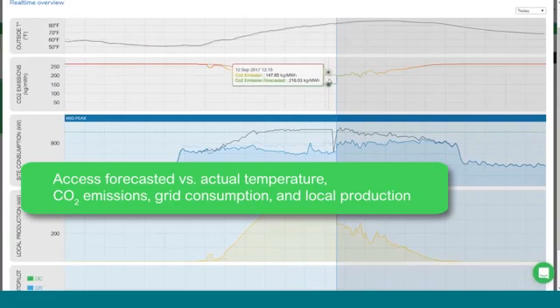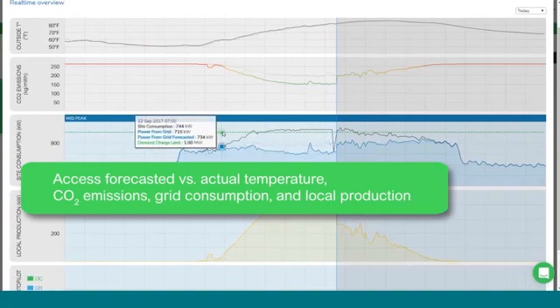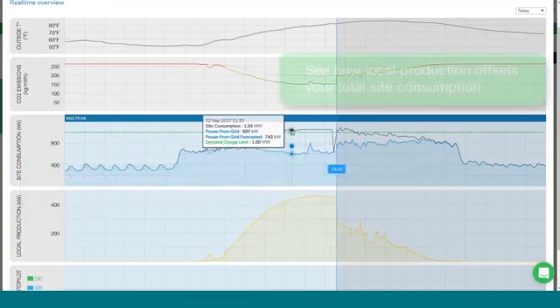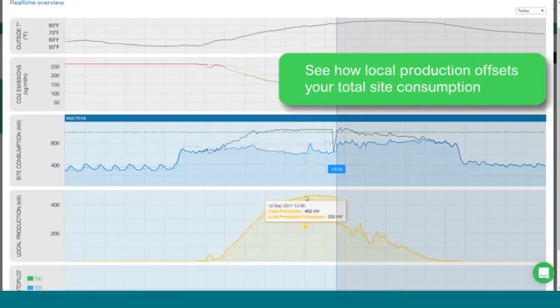Coming down here, we can see our site consumption. The green line indicates our demand charge limit of one megawatt from the grid. The blue line is power from the grid versus power forecasted. And as you come over, you can actually see we used more than our demand charge limit, but looking down here, we have local production from our solar array that offset what we were accepting from the utility feed, so we were actually able to stay well under our demand charge limit because of our PV array.